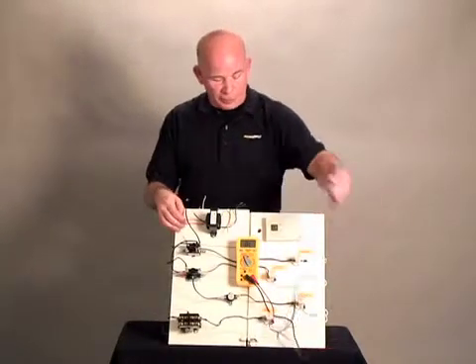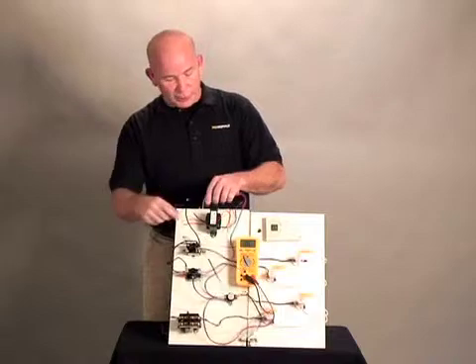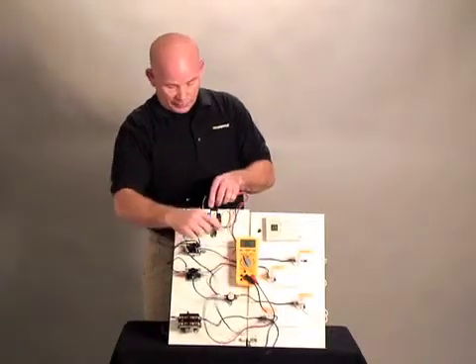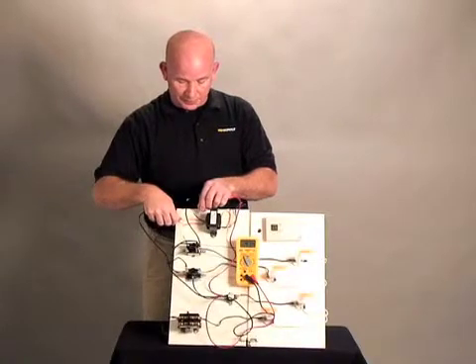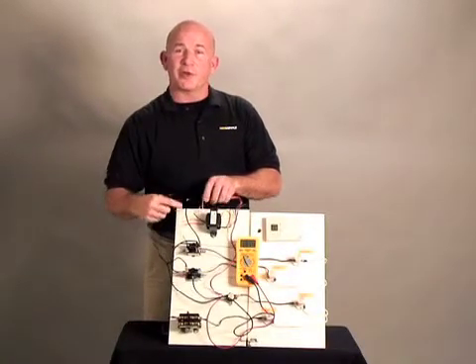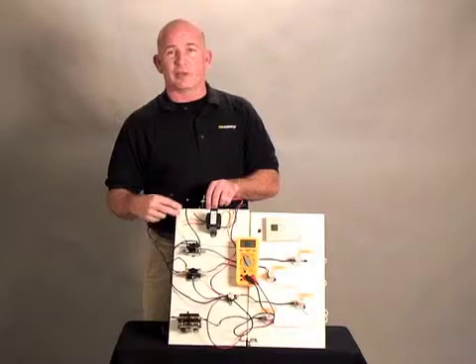To test the primary side, you always check continuity after you set your meter to continuity from your common to the other three wires, and all three of these toned so we know that this side is working.